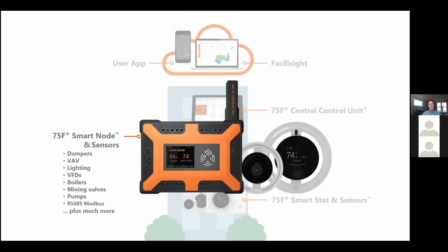The other device at the device level we're talking about here is what we call a smart node. This is more of a generic I/O type device with analog and digital relay I/O, and it's what we use for all the other terminal devices not controlled by a thermostat, like a VAV box, for example. We'd put this controller on the VAV box, or any damper or VFD, or anything that needs to be scheduled. Boilers could be enabled, disabled, put on a schedule with outside air temperature reset, or whatever is needed—these are all done with this other device.